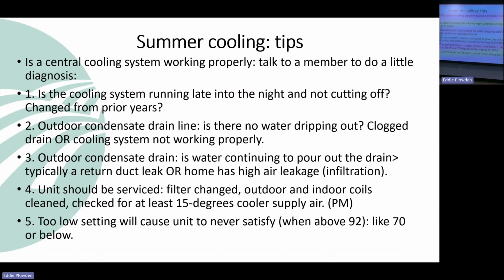And to finish up on the energy tips and talking to members on it. I put the summer tip slide on here, but some of it obviously works with the winter also. Is the cooling or heating system working properly? The cooling system, is it running late into the night and not cutting off? Same thing with the heat. Is it running more this year than it was last year? Outdoor condensate drain line in the summertime: the cooling unit is actually taking the humidity out of the air and then draining it out through that condensate line. If it's stopped up, or if the coil is not charged properly, it won't be condensing any moisture whatsoever. So that's a problem with the unit.